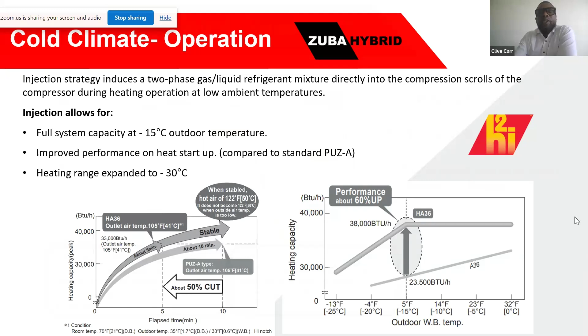This is an improved application to air source heat pump in a hybrid application, where a smart thermostat can be used for dual fuel switching, determining the ideal timing in which it is best suited to switch from heat pump operation to fossil fuel operation. And this is done taking into consideration a few different factors that are built into the algorithm for switching.